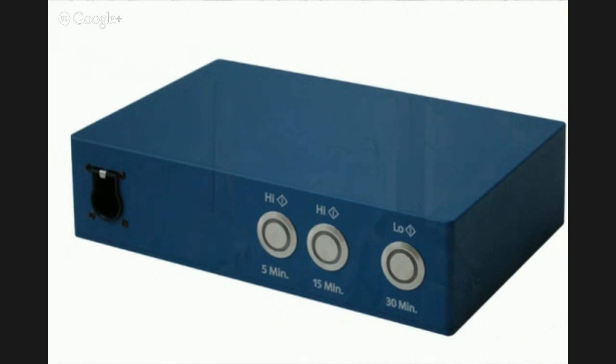Now, the way that comes into play is devices are approved by the FDA by design, color, and use. So you have to get a specific device approved. We will then be able to achieve what they call predicate approval on similar devices in our line that meet the FDA requirements. For example, one of the issues we've had in the past is that the equine unit being in a plastic case for protection and durability is, I wouldn't say flammable, but it will melt in a flame or in a fire. And so that precludes that particular case from being FDA approved. However, those regulations are changing all the time, and we are working to approve things all the way across the line. But primarily, as far as FDA approval is concerned, it will be the office unit in the Mia configuration.